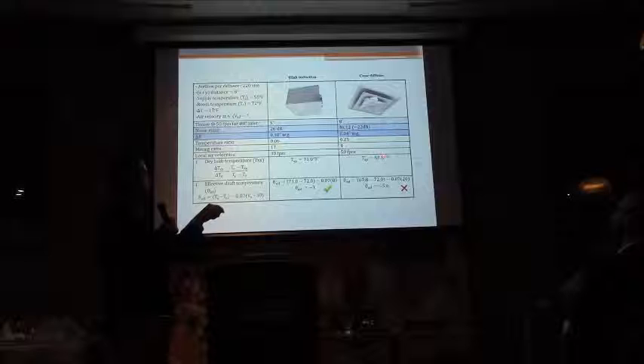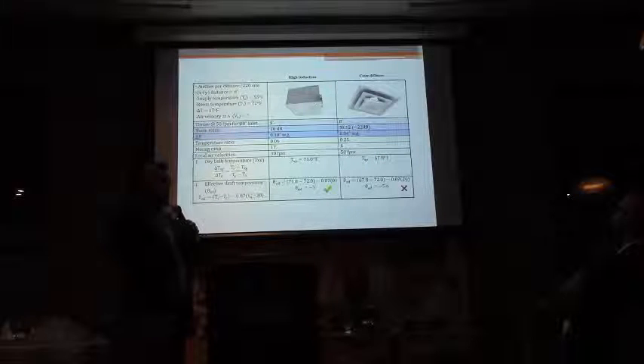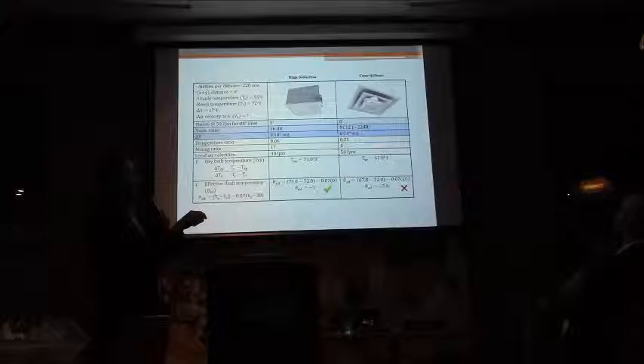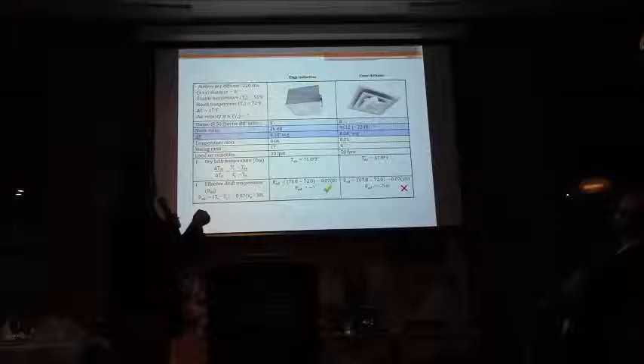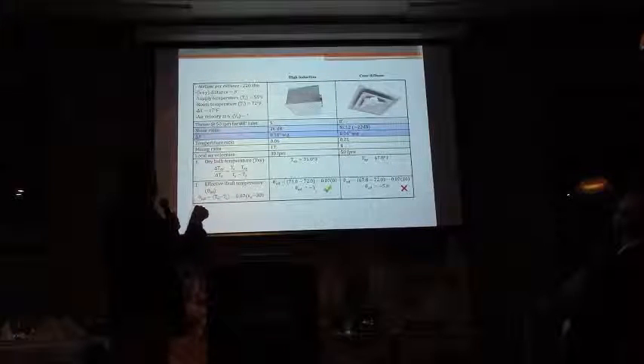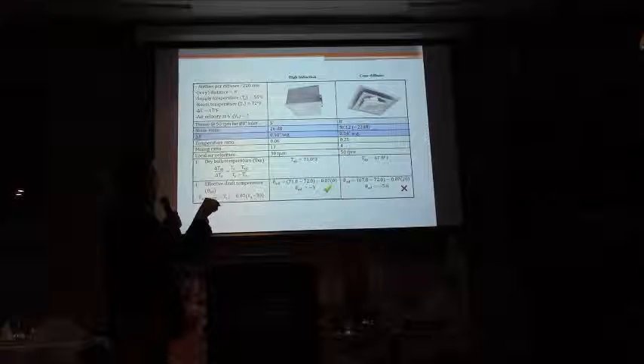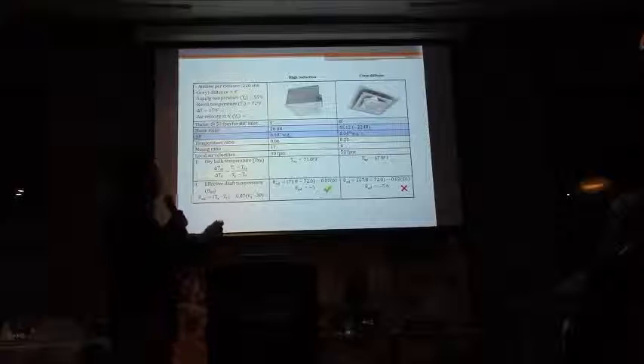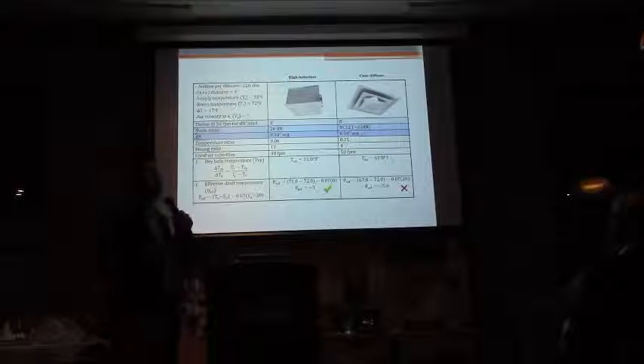So the temperature here is 71. I found it with this formula. This one here is 67.8. So first of all, you're reaching the occupied zone at temperatures much colder with the cone diffuser than with the high induction. And the second thing is, if you do the effective draft temperature calculations, your effective draft temperature here is going to be -1, because you reach at 71, minus 72, and there's no velocities because you actually reach the zone at 30 feet per minute, while this one here is at -5.6, the effective draft temperature. So that's a fail for the cone diffuser.